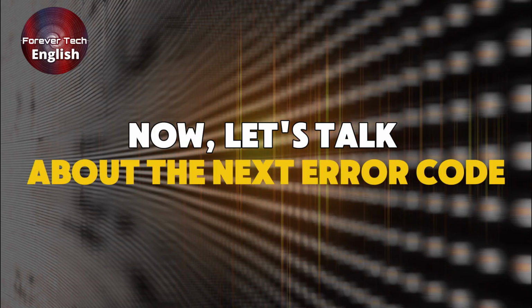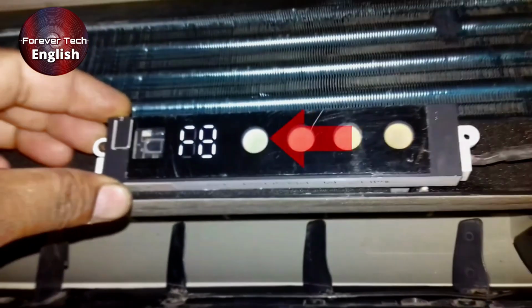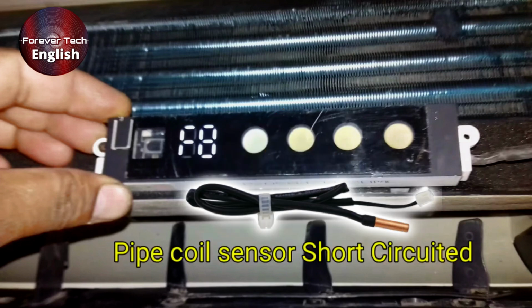Now, let's talk about the next error code, which is F8. Let me explain why the F8 error appears on the display. This error occurs when the pipe coil sensor becomes faulty or short-circuited.